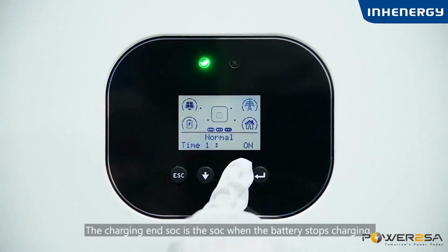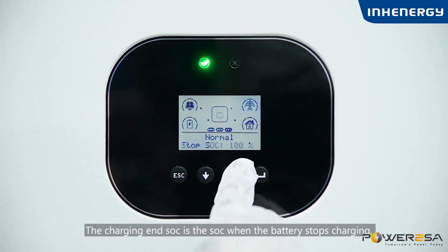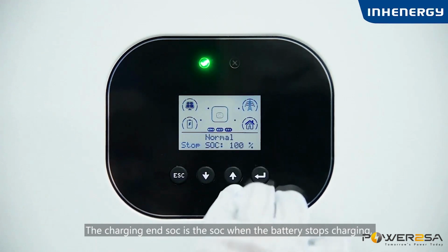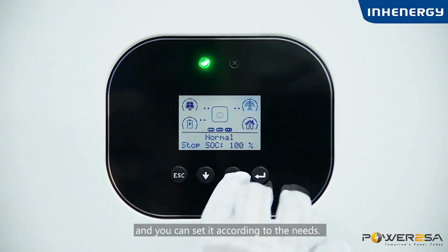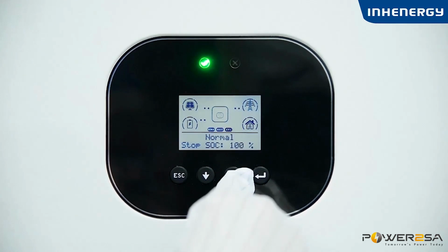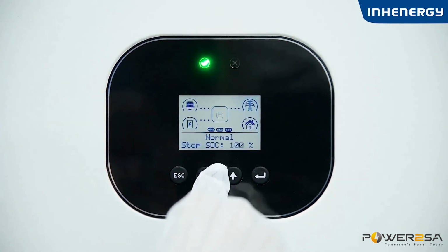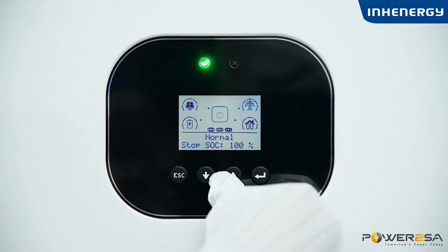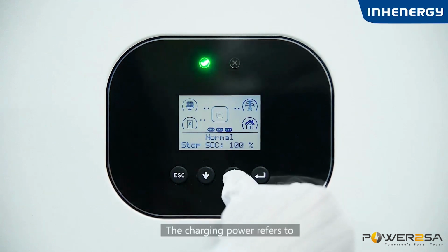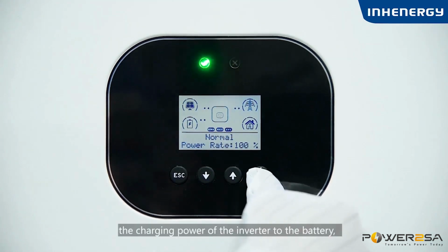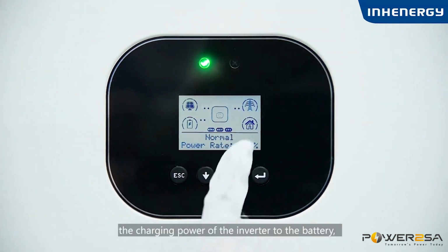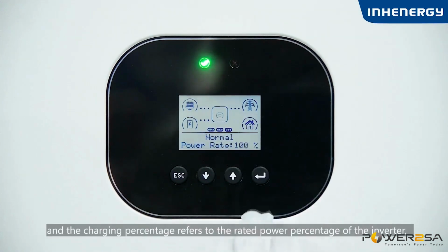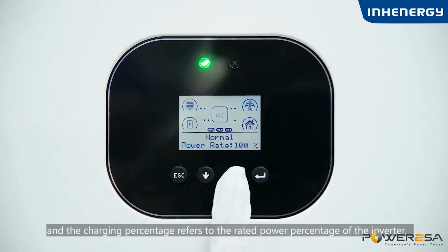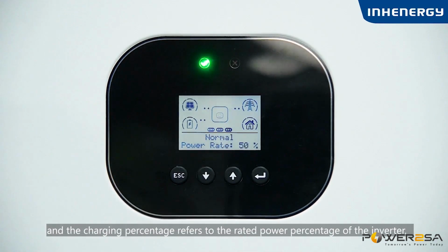The charging end SOC is the SOC when the battery stops charging, and you can set it according to the needs. The charging power refers to the charging power of the inverter to the battery, and the charging percentage refers to the rated power percentage of the inverter.